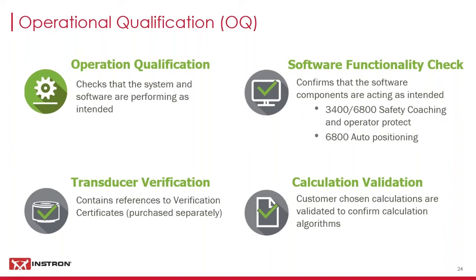When a customer purchases Instron IQOQ, they work with the sales team to choose the specific calculations that they are using in the software for their specific testing needs. The chosen calculations are then included in the calculation validation section. To validate a calculation, the Bluehill algorithm is duplicated in Microsoft Excel and then checked against the result from Bluehill. For all components of the Instron OQ, documented evidence is provided where appropriate. This ensures that the Instron IQOQ documents are robust and contain the necessary objective evidence for review during an audit. As Jim mentioned earlier, from the FDA perspective, if it isn't documented, it didn't happen.